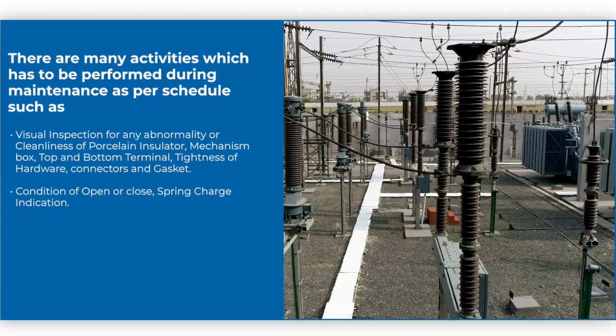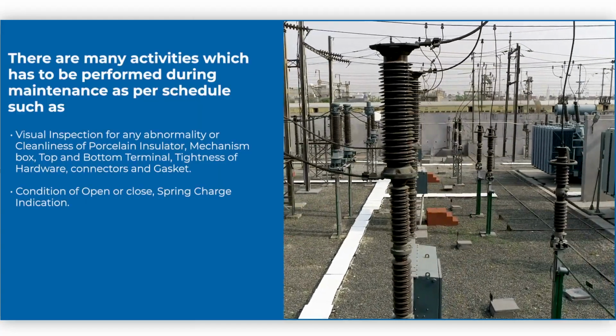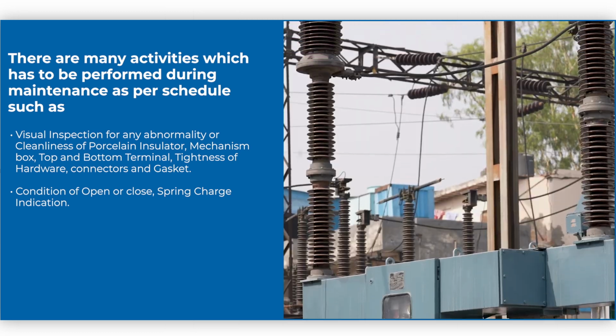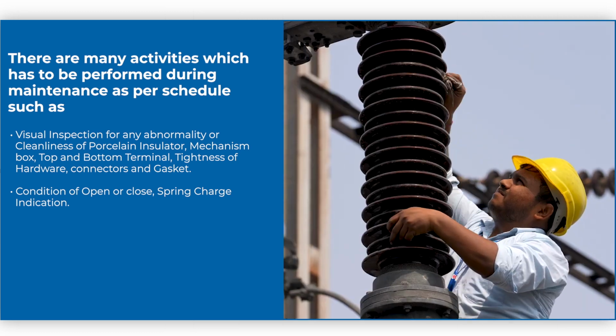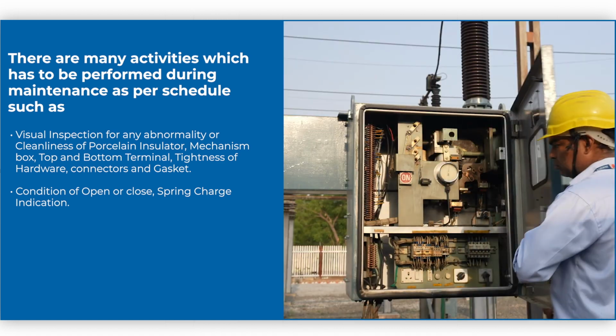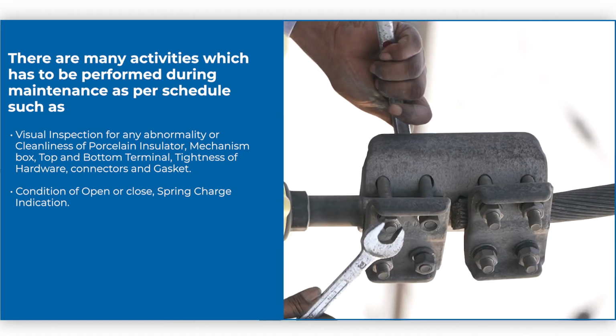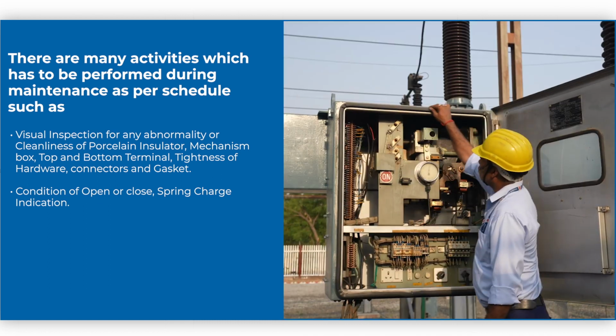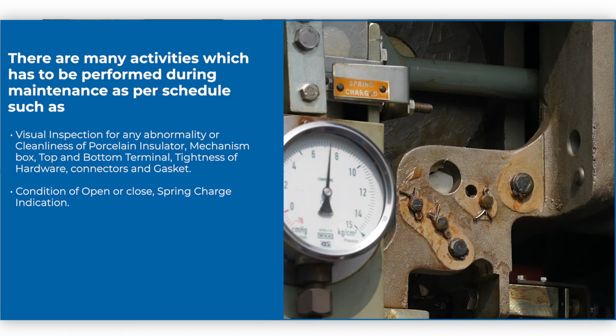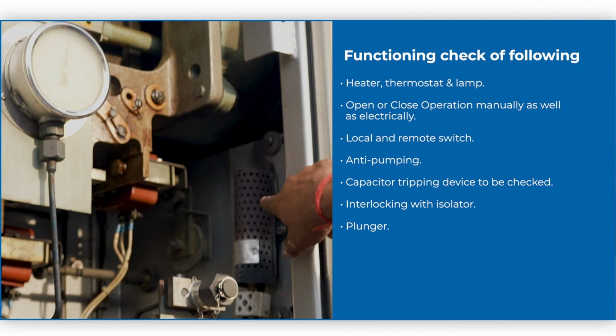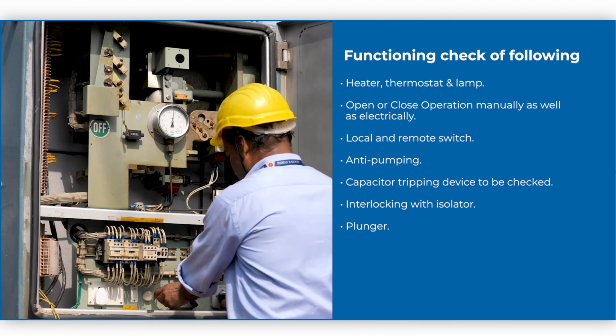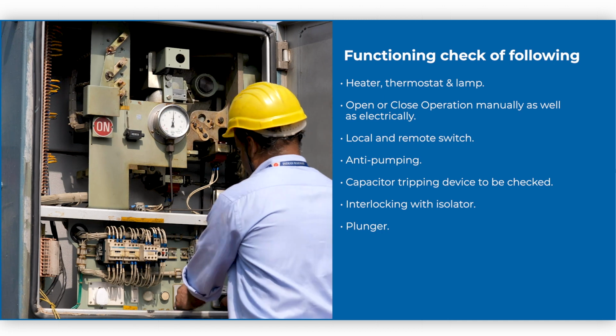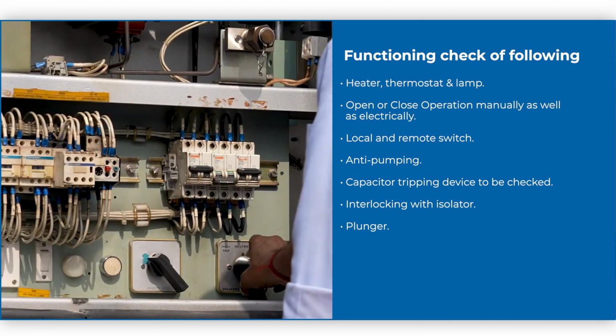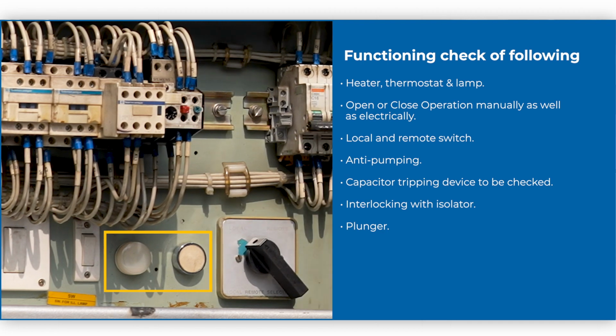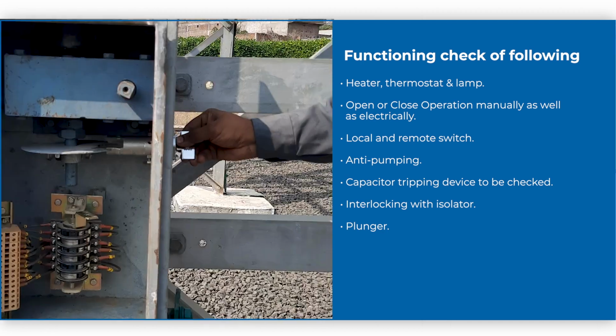There are many activities that have to be performed in the maintenance schedule, such as visual inspection for any abnormality or cleanliness of porcelain insulator, mechanism box, top and bottom terminal, tightness of hardware and connectors and gasket, condition of open or close, spring charge indication. Functioning check of following: heater, thermostat and lamp. Open or close operation manually as well as electrically. Local and remote switch. Anti-pumping. Capacitor tripping device to be checked. Interlocking with isolator, plunger.